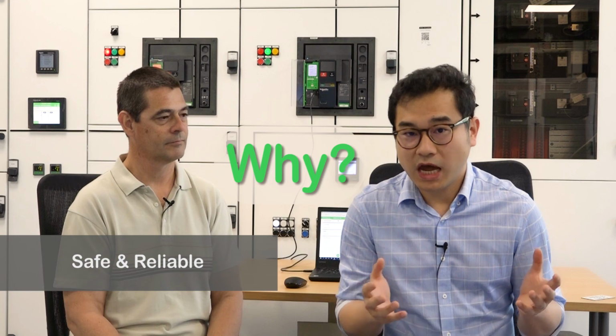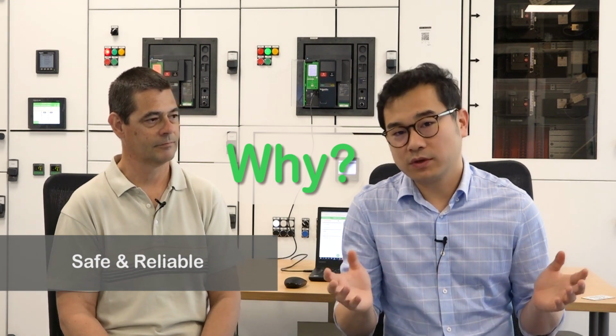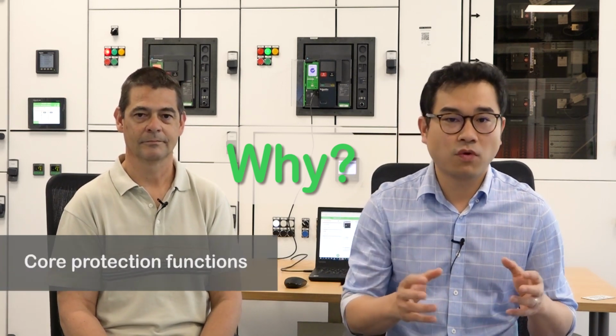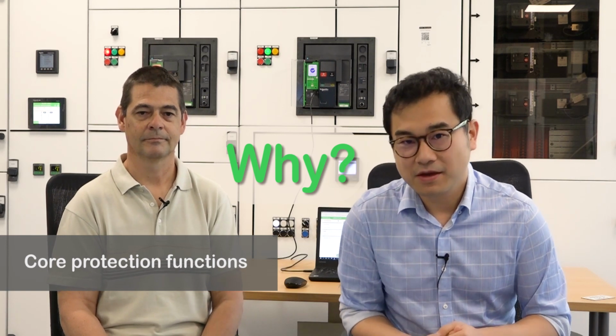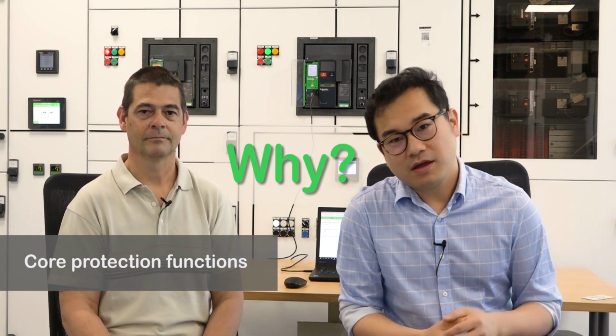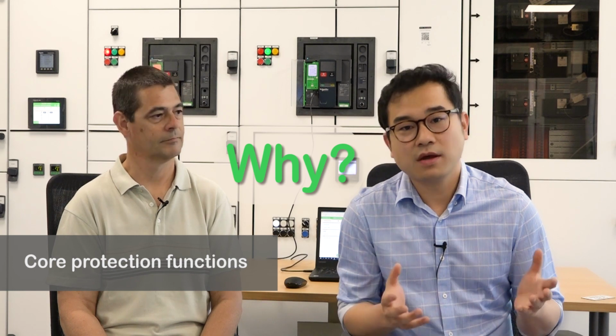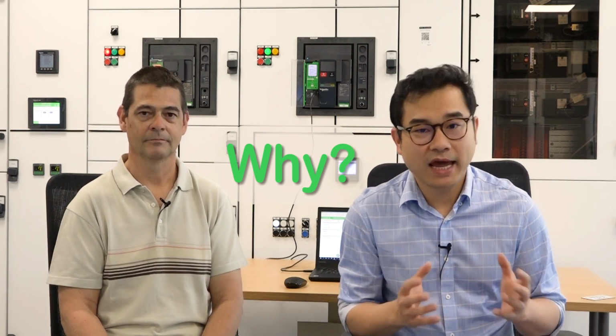Well, circuit breaker testing is essential to ensure the safe and reliable performance of the electrical installation. The primary goal of circuit breaker testing is to determine the condition, especially its core protection functions. Given the circuit breakers may be inactive for months or years prior to the fault, a regime of circuit breaker testing is an important safety factor.